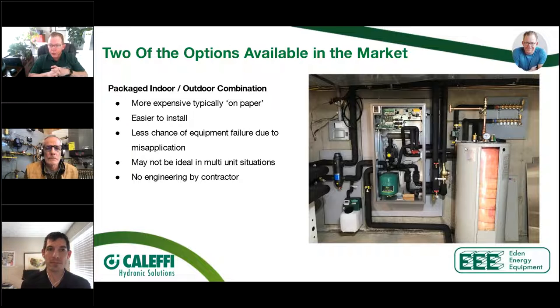So on paper, this is more money. But again, it's on paper. The reality is this could be an easier installation for you, because what you end up doing is you literally just mount this indoor unit on the wall. It has two ports to hook up your outdoor unit, clearly labeled. It has your heating and cooling connections clearly labeled, and it has your domestic hot water connections clearly labeled. You don't need any extra pumps. You don't need any diverting valves. You don't need any controls. This is a fully packaged solution.